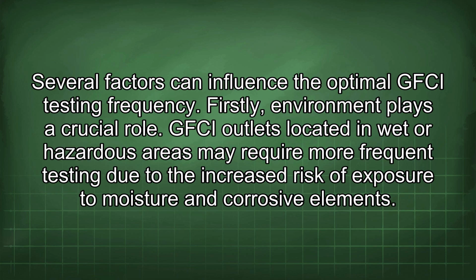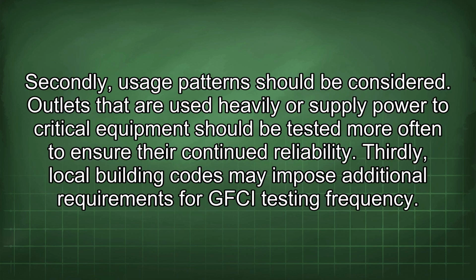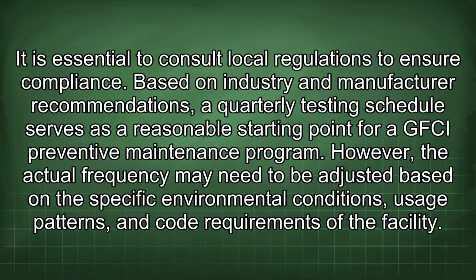Several factors can influence the optimal GFCI testing frequency. Firstly, environment plays a crucial role. GFCI outlets located in wet or hazardous areas may require more frequent testing due to the increased risk of exposure to moisture and corrosive elements. Secondly, usage patterns should be considered. Outlets that are used heavily or supply power to critical equipment should be tested more often to ensure their continued reliability. Thirdly, local building codes may impose additional requirements for GFCI testing frequency. It is essential to consult local regulations to ensure compliance.